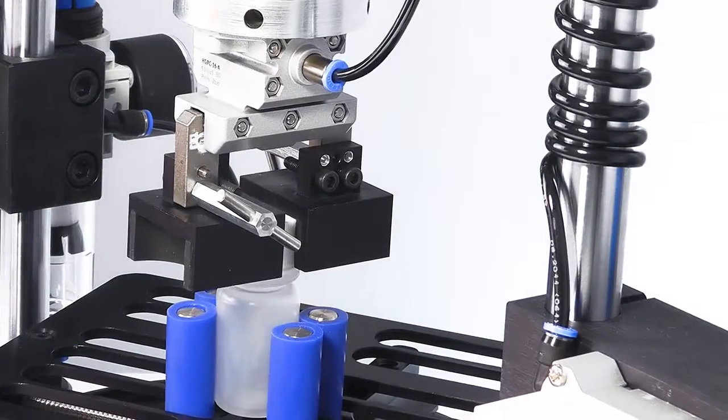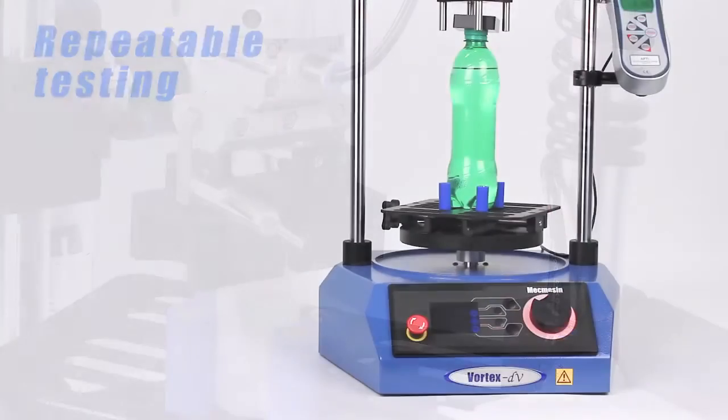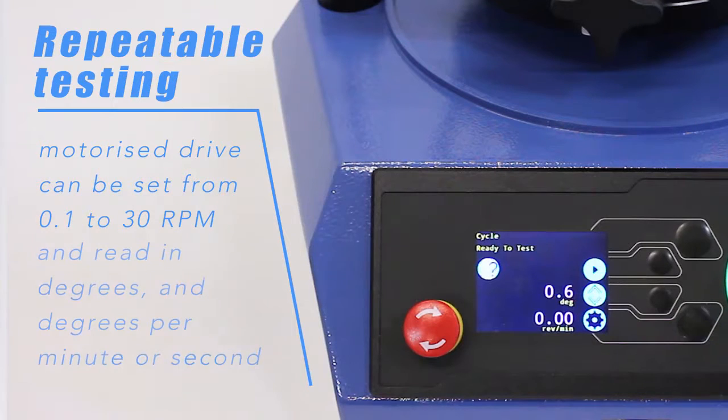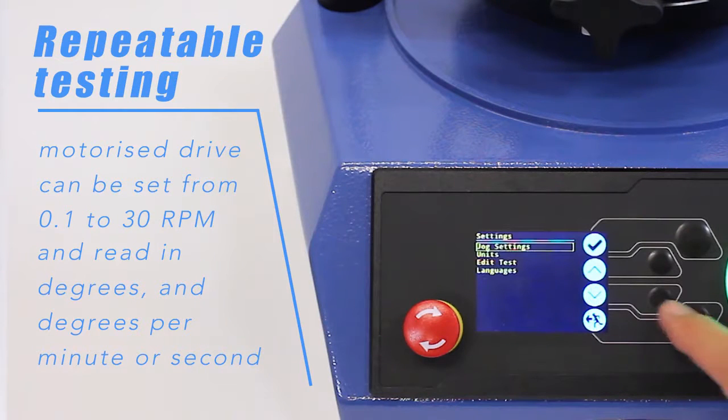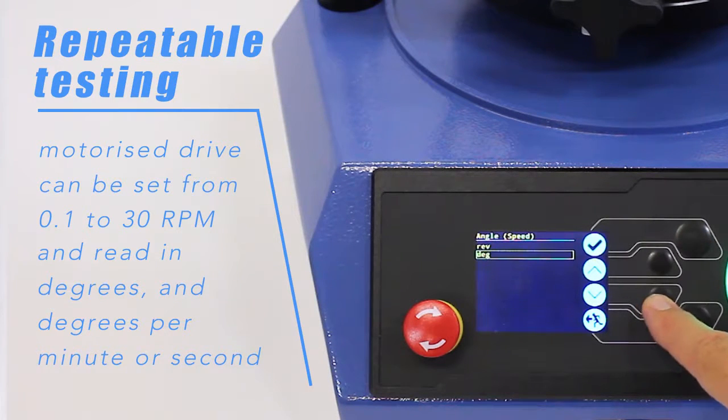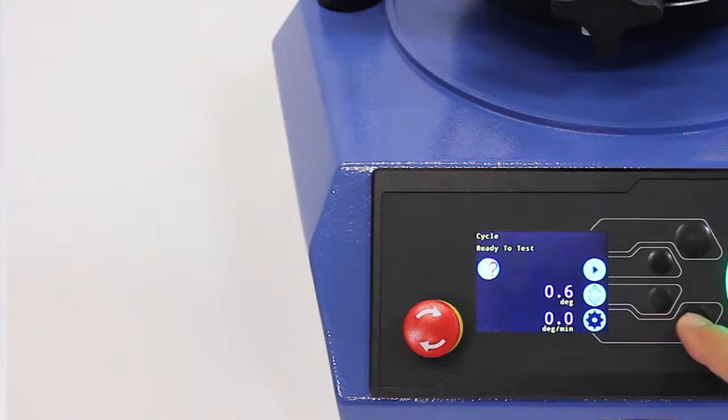To achieve repeatable results, the motorized drive rotates at a constant speed which can be set from 0.1 right up to 30 RPM. Depending on your preference, angular measurement can be reported in either revolutions or degrees. Speed may be set in either degrees or revolutions per minute or second.